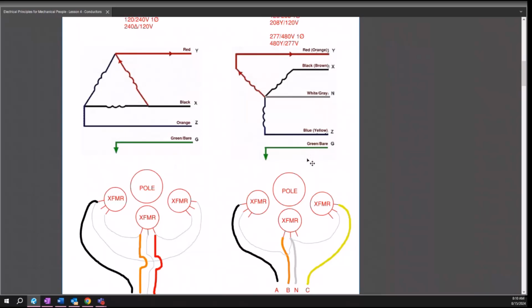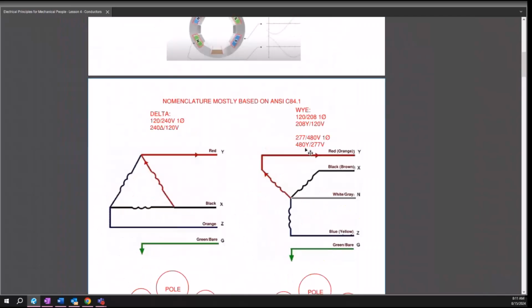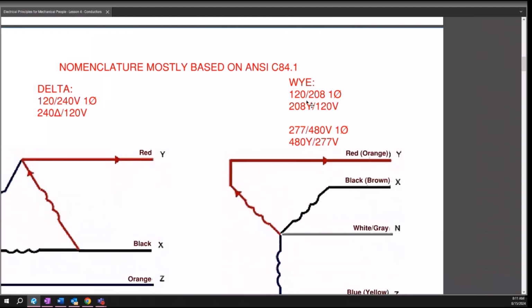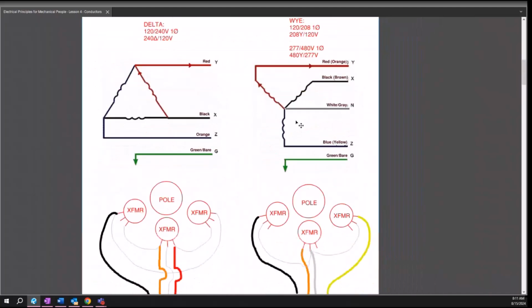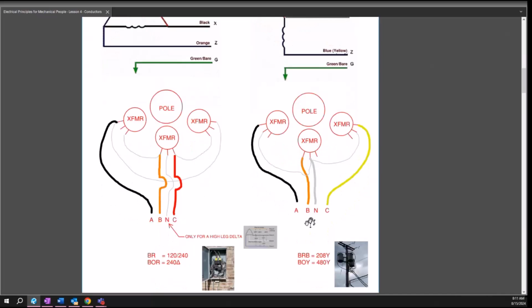The code recognizes this ANSI standard of the coloring of wires. The ANSI standard is how it is written. Where does that standard come from? So the coloring suggestion comes from the NEC, with the exception of the high leg orange, white and gray being neutral, green or bare being ground. Gotcha. That's an NEC standard. You shall have this color. Gotcha. Now, local jurisdictions can actually overwrite the phase conductors, especially on a 208 or 480 system.